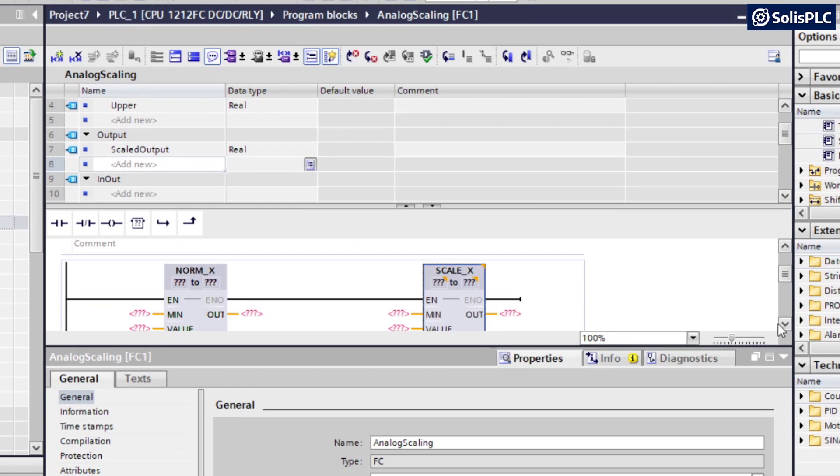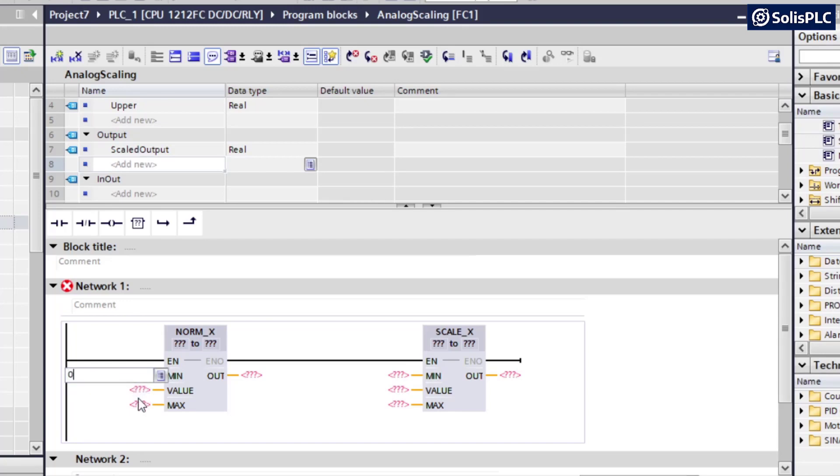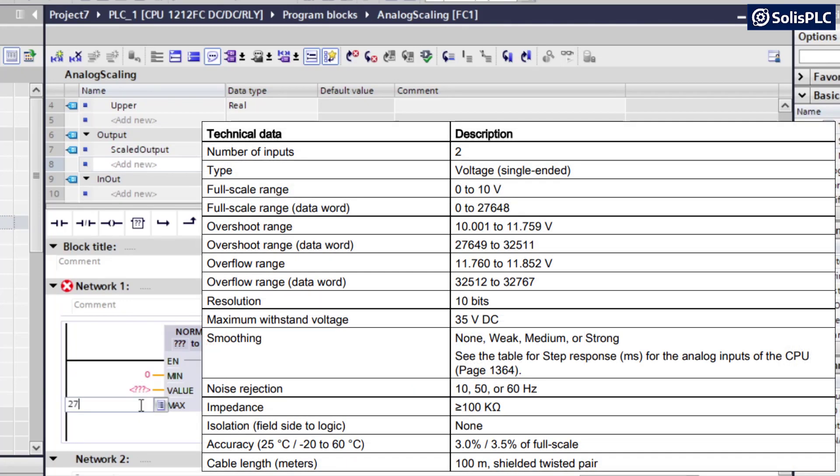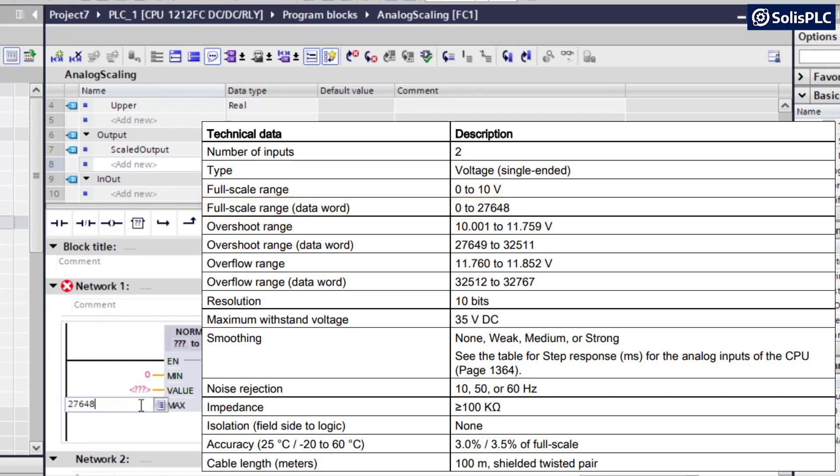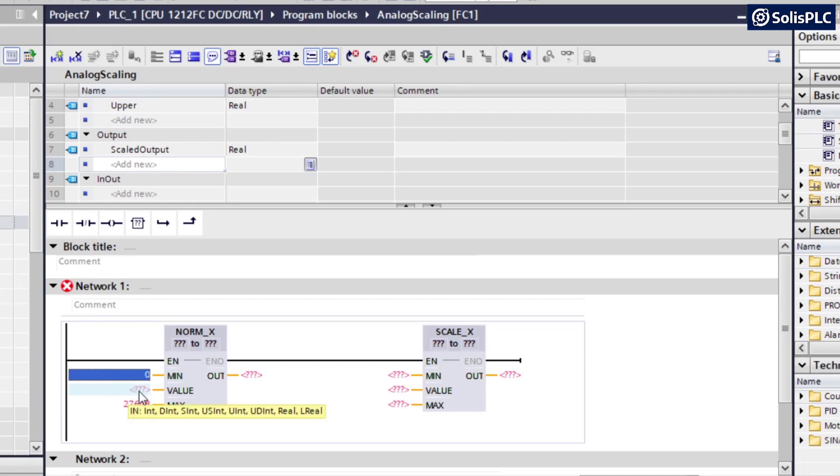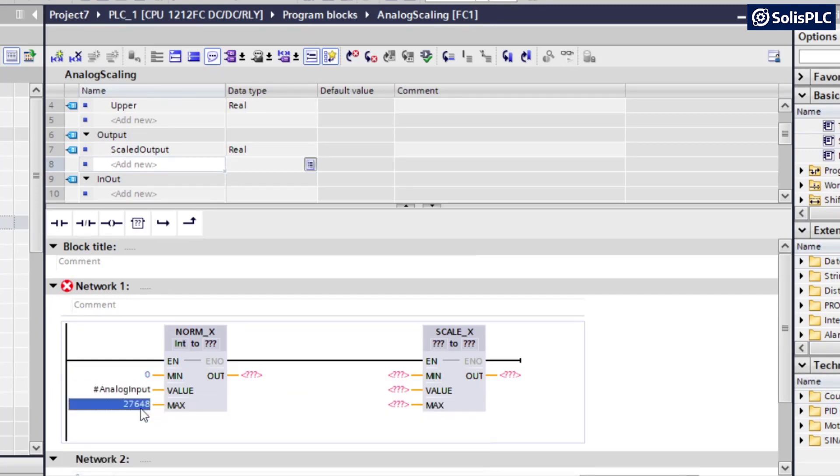And so let's take a look at the parameters. I'm just going to slide down this window if you're following along. So on the minimum side, we are expecting a value from 0 to 27,648. So that's going to be the range of the raw value that we're expecting on that specific input. And here, this is going to be input, analog input, analog input.